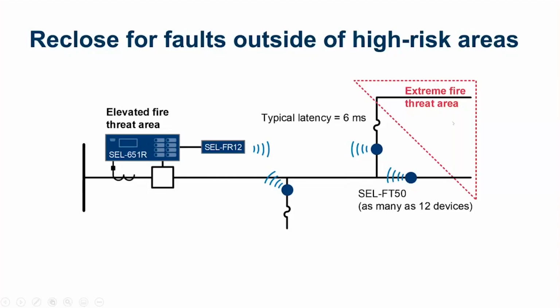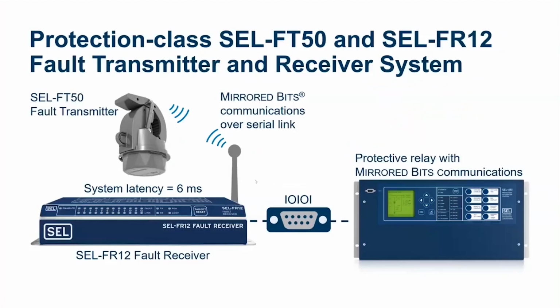So what can I use in such a case? I can use these faulted circuit indicators, which are installed on the overhead conductors. What these faulted circuit indicators do is detect the fault and send a signal to a receiver. This transmitter is called FT50 and the receiver is called FR12. Once the transmitter sees a fault, it can send the signal to the FR12, and then the FR12 can send the signal to the 651R, letting it know to either block reclosing or allow reclosing, depending on what area the fault is in. So this is what the FT50 and FR12 look like.